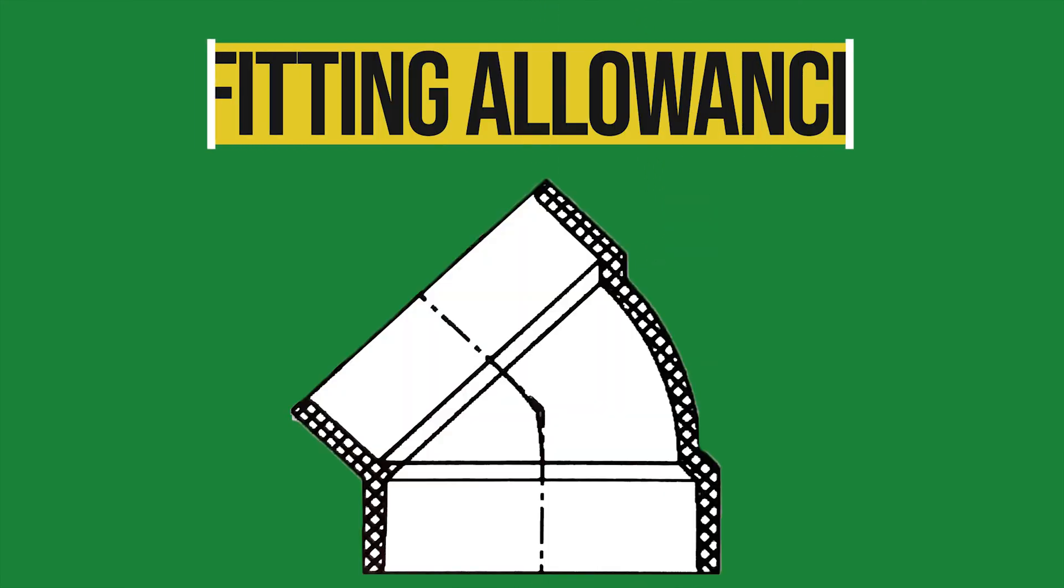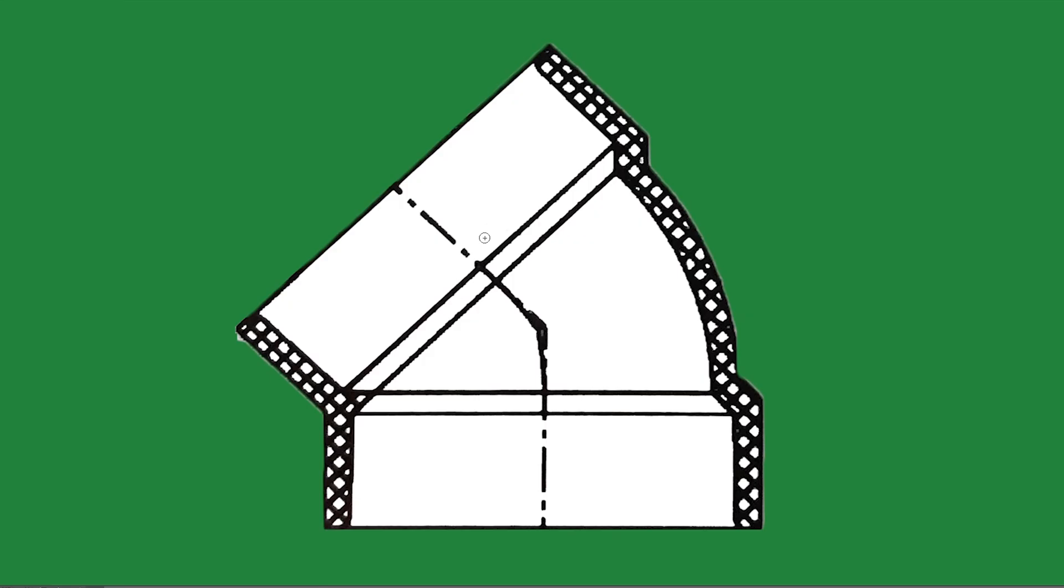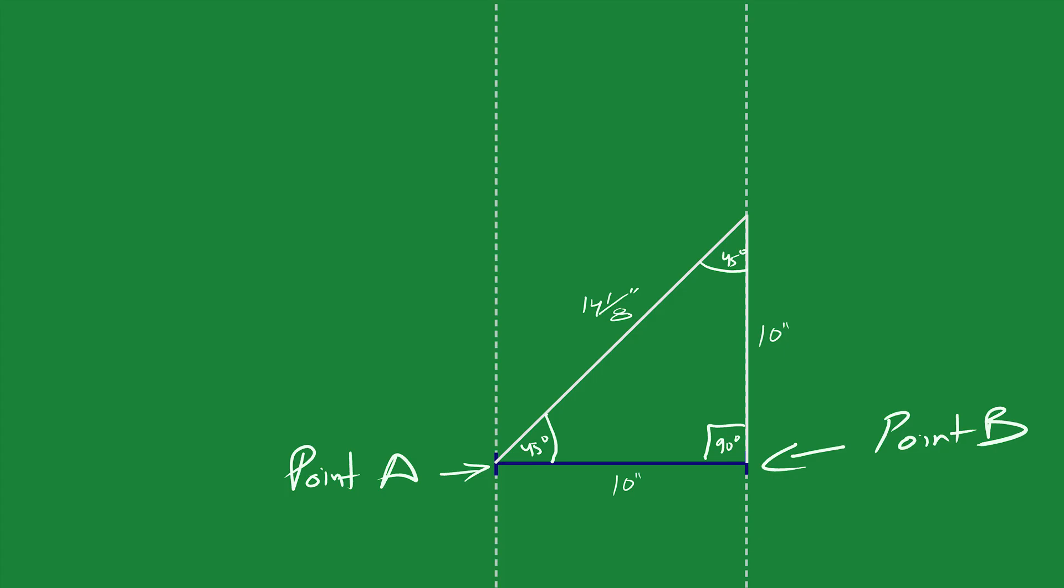Because there's one more step from here called the fitting allowance. To measure the fitting allowance, mark the center of the fitting and end of the hub. In our case it's a quarter inch. Now subtract a quarter inch twice because we are using two fittings. So 14 and 1/8 minus 2 quarters, so the final measurement will be 13 and 5/8.